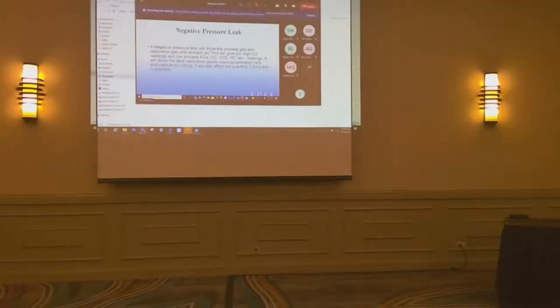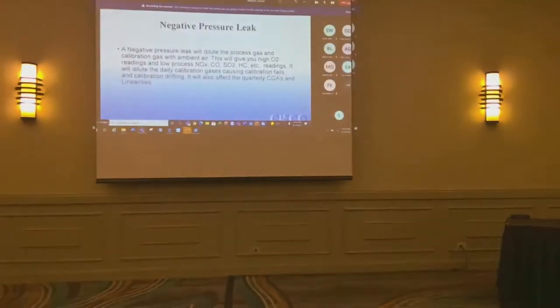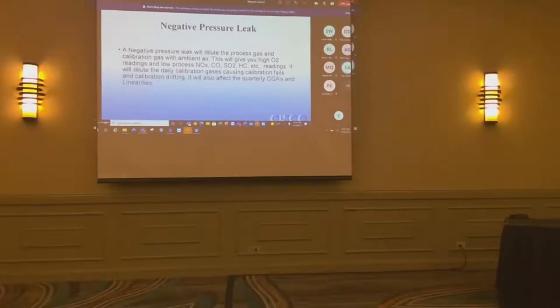Let's talk about the negative pressure leak. A negative pressure leak will dilute the process gas and calibration gas with ambient air. This will give you high O2 readings and low process values, your NOx, CO, SO2, hydrocarbons, etc. It will dilute the daily calibration gases, causing calibration fails, calibration drifting. It'll also affect the quarterly CGAs and linearities. And sometimes they don't show up until we do our quarterly stuff.